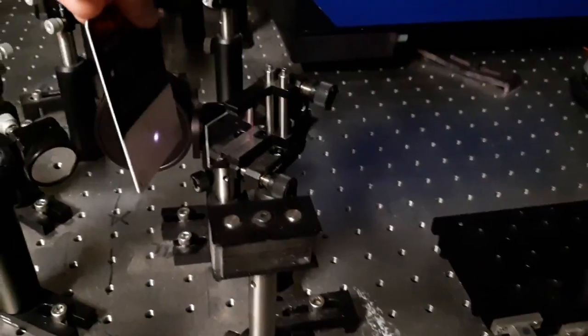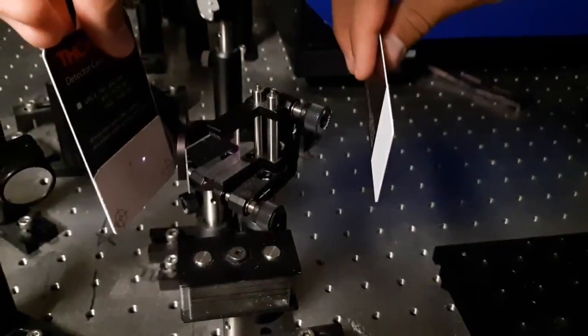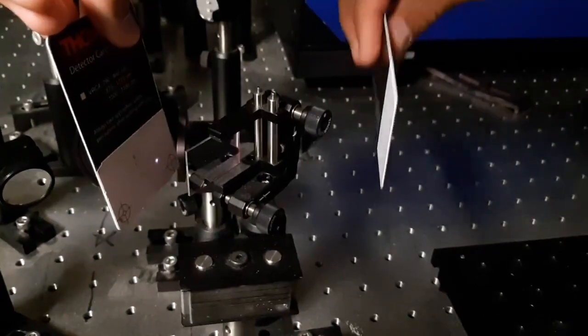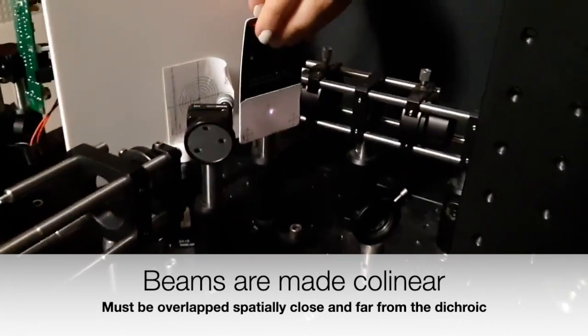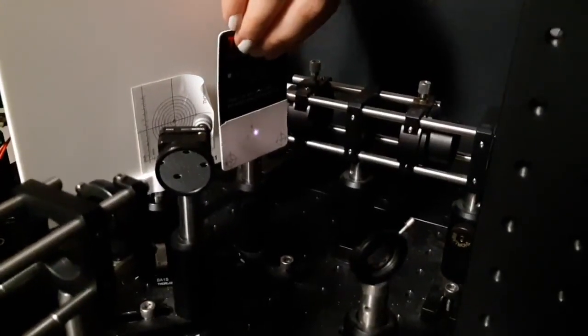The goal is to recombine the 1064 and the 816 beam at the dichroic so that they are collinear when going into the microscope. A quick check shows that if they are overlapped near the dichroic and overlapped far from the dichroic, they should be almost collinear. Almost collinear. Is that sufficient? We're talking about 2 pulses that are 6 picoseconds in length, that is only a few millimeters in space, that have different wavelengths, and that must focus through a high NA objective at the same place at the same time.